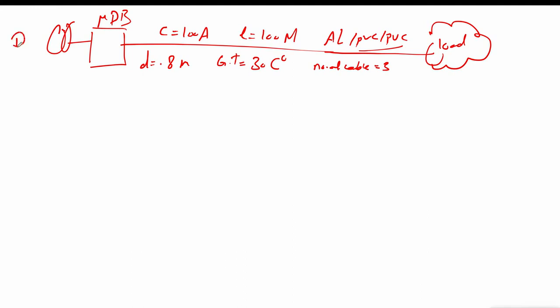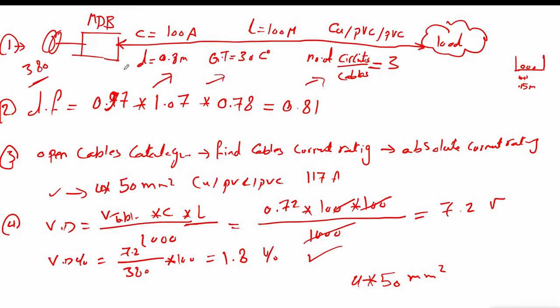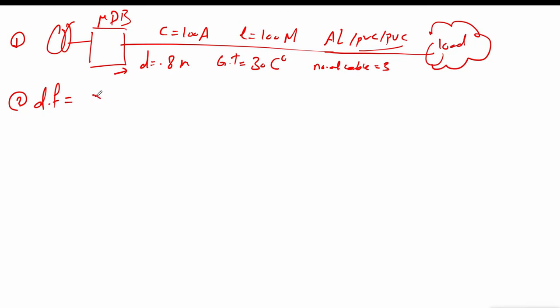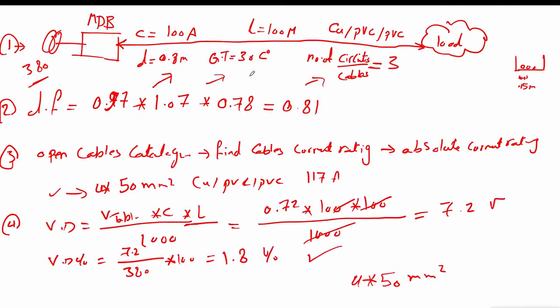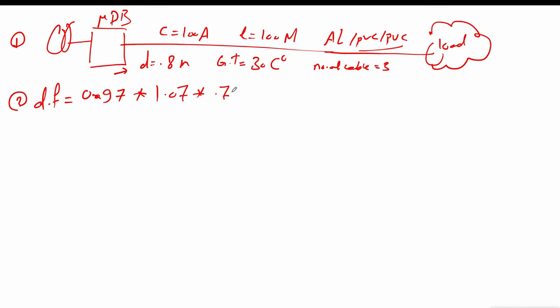Step two: calculate the rating factor. For the same installation conditions, the rating factor for aluminum shall be the same as for copper, because the correction factors relate to installation conditions, not the conductor type. We have rating factors for installation depth, ground temperature, and grouping. The final combined rating factor equals 0.81.